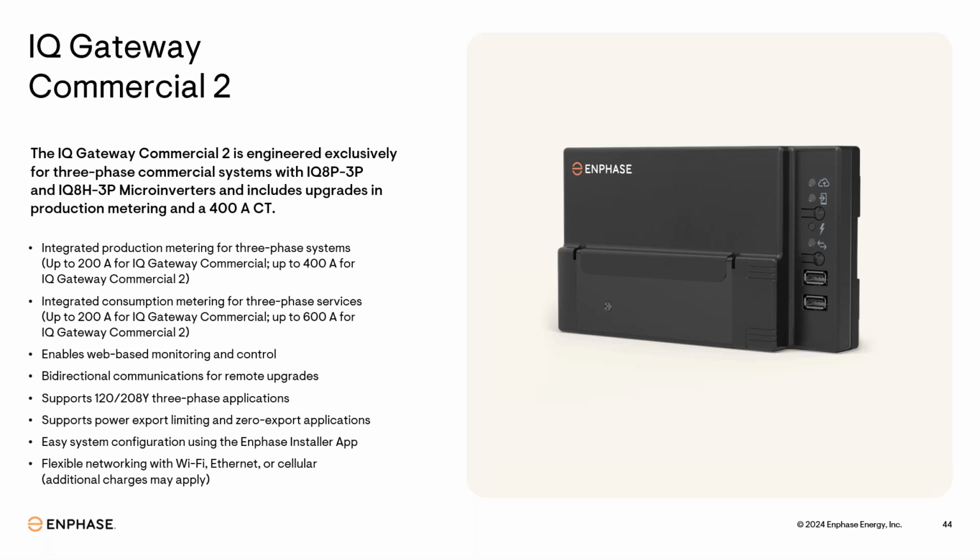This new gateway 2 is improved over our old commercial gateway 1. With the old commercial gateway 1, you could connect up to 249 micros to the gateway. With gateway 2, you can connect up to 276 micros. 276 micros is approximately 150 kW DC. That's not a limit on your project size.